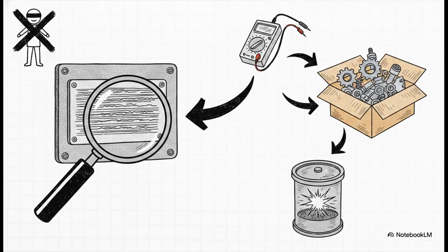Model ID first, procedure second. I really want to emphasize this right off the bat. Before you even think about touching a single test point with your meter, you've got to know exactly which breaker family you're dealing with, because everything else cascades from that one piece of information. Your test procedure, your spare parts strategy, and even the arc extinction medium working inside that sealed unit all depend on whatever model is stamped on that nameplate. If you get the ID wrong, you're just flying blind, and in medium voltage marine applications, that's a risk we just can't take.